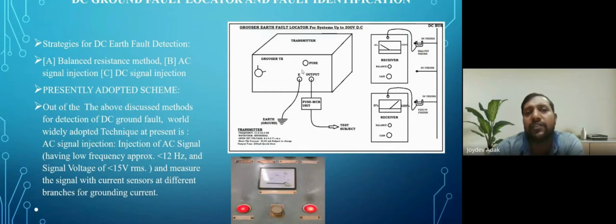This is a transmitter. It creates the signal, and we are injecting this signal into the DC bus. We connect the receiver to different branches of the DC circuit. If any branch has a faulty part or a grounding condition, then the receiver deflects to its highest value. This is the deflection, and here there is no deflection.